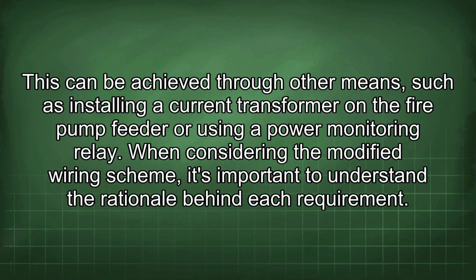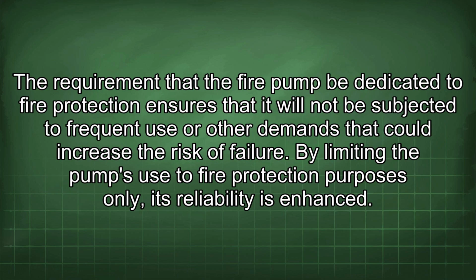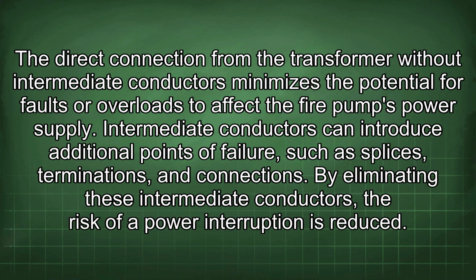When considering the modified wiring scheme, it's important to understand the rationale behind each requirement. The requirement that the fire pump be dedicated to fire protection ensures that it will not be subjected to frequent use or other demands that could increase the risk of failure. By limiting the pump's use to fire protection purposes only, its reliability is enhanced. The direct connection from the transformer without intermediate conductors minimizes the potential for faults or overloads to affect the fire pump's power supply. Intermediate conductors can introduce additional points of failure such as splices, terminations, and connections. By eliminating these intermediate conductors, the risk of a power interruption is reduced.